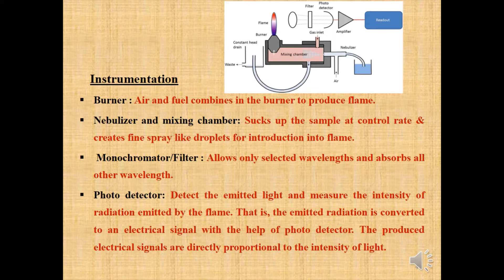Pressurized air is first passed through the nebulizer. The nebulizer sucks the sample at a controlled rate and creates a fine spray of droplets which pass through the mixing chamber. In the mixing chamber, mixing of the sample with LPG gas takes place — LPG gas is supplied from the gas inlet. Next, the mixture is passed through the burner where burning of the mixture takes place.